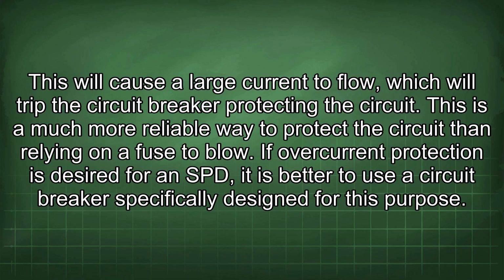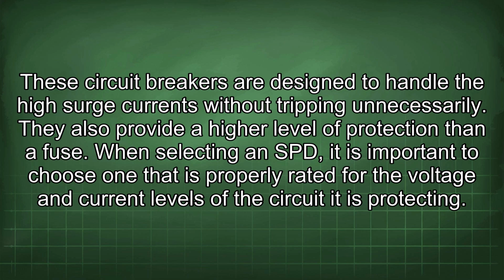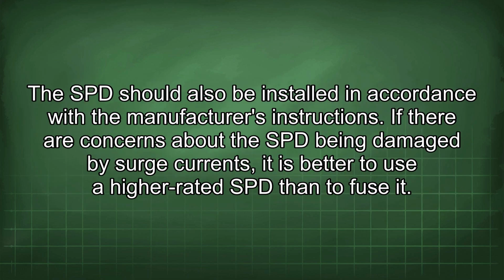If overcurrent protection is desired for an SPD, it is better to use a circuit breaker specifically designed for this purpose. These circuit breakers are designed to handle the high surge currents without tripping unnecessarily. They also provide a higher level of protection than a fuse. When selecting an SPD, it is important to choose one that is properly rated for the voltage and current levels of the circuit it is protecting. The SPD should also be installed in accordance with the manufacturer's instructions. If there are concerns about the SPD being damaged by surge currents, it is better to use a higher rated SPD than to fuse it.